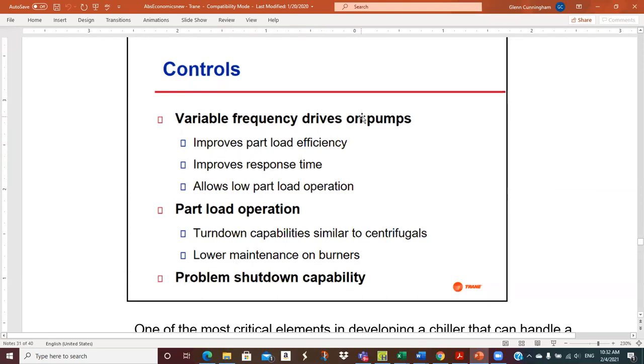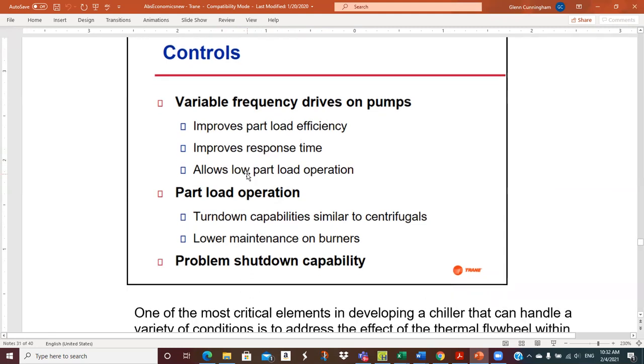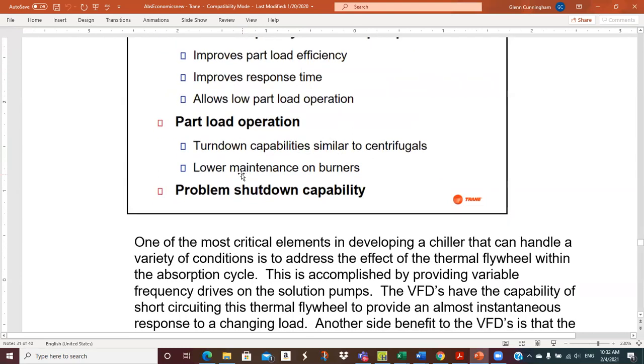But they put VFDs on their pumps. Part load efficiency is better. Response time is very quick, and it has allowed lower part load operation, which we'll get into on some of these notes down. Part load turn down is now similar. By turn down, it's of your rated capacity, what's the lowest percent that you can still operate the machine? For example, if you had a 1,000-ton chiller, can you operate it at 200 tons? Can you operate it at 150 tons?